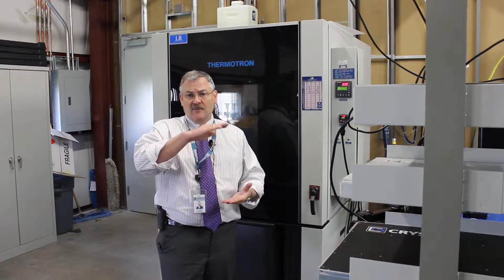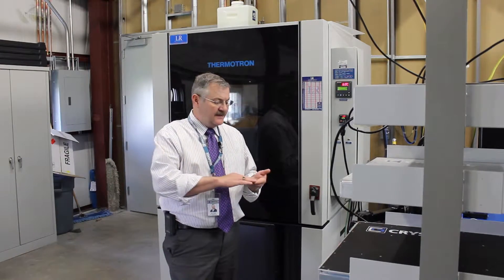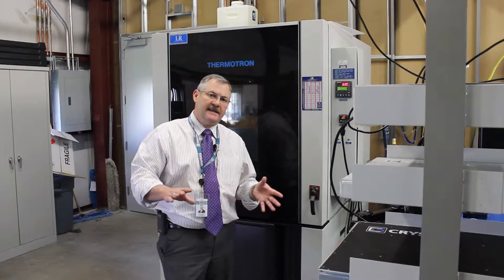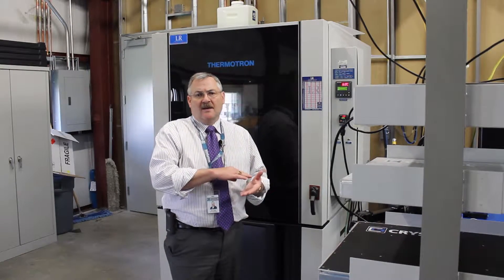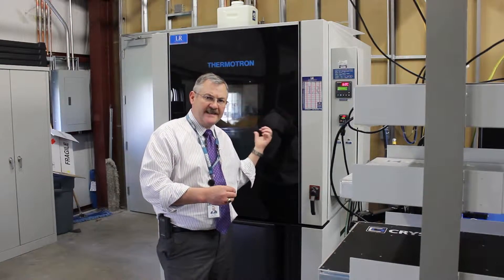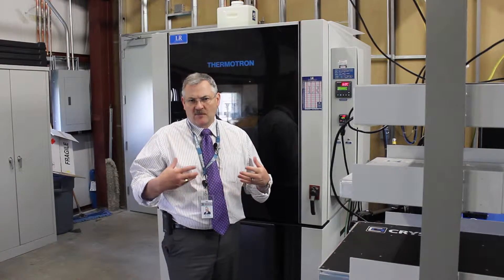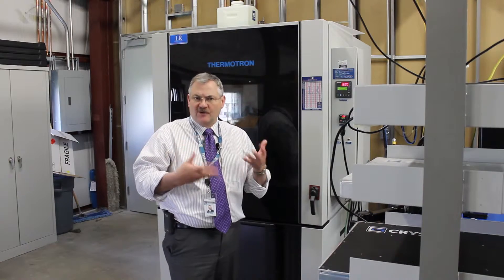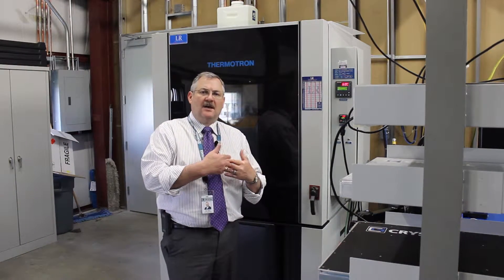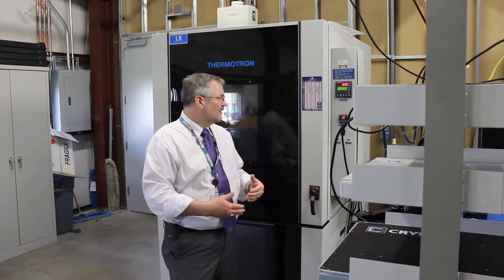You cycle for 24 hours, and the standard humidity test — which they call aggravated — is a 24-hour test for 10 days. What we do at Crystal Group to prevent damage from this kind of environment is apply conformal coating and a special kind of staking, ruggedizing the components internally so they'll withstand that environment.